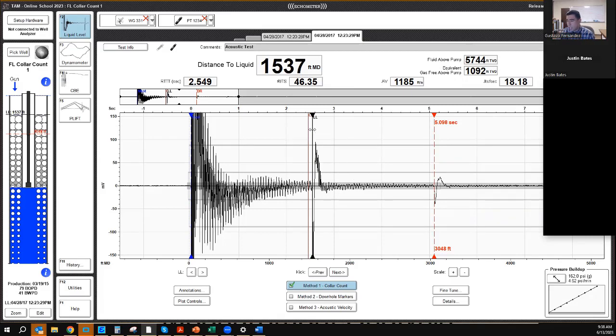What's next? Calculating distance to liquid. How do we do that? At this point, by moving the liquid level line or selecting the liquid level kick, we have a 2.55 second time. Somehow the software converted 2.55 into distance. How did it do that? By knowing the speed, how fast that wave was traveling. The software has calculated 1185 feet per second.